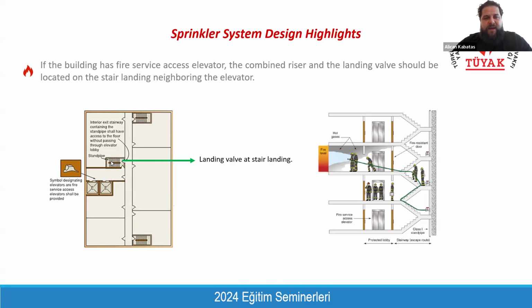Why are we locating the landing valve within the stair instead of the fire protection lobby? Because there can be a water leakage from these landing valves, and if the water leaks within the lobby, it can reach the elevator well, and it can cause a failure of the elevator. That's why instead of placing these landing valves into the fire protection lobby, we prefer to place them within the fire escape stair. So in case of any leakage, the water will not come into the lobby. Instead, it goes down the stairwell.